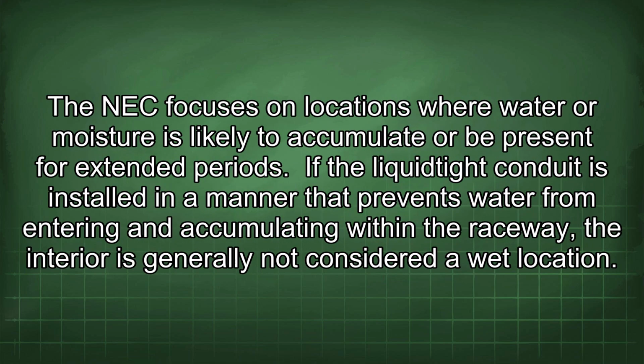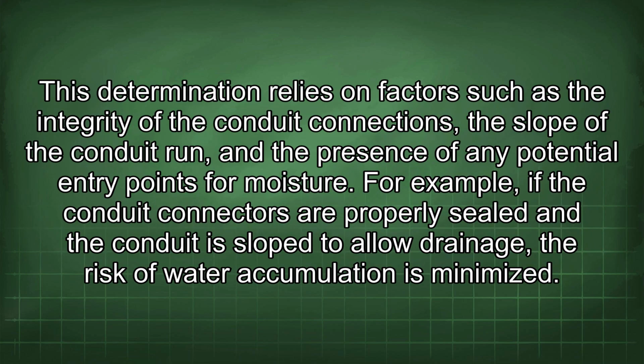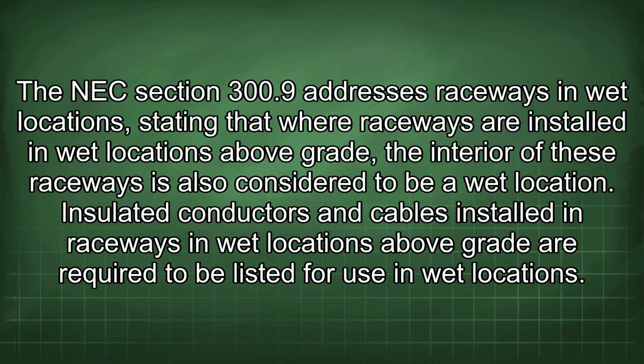The NEC focuses on locations where water or moisture is likely to accumulate or be present for extended periods. If the Liquidtight conduit is installed in a manner that prevents water from entering and accumulating within the raceway, the interior is generally not considered a wet location. This determination relies on factors such as the integrity of the conduit connections, the slope of the conduit run, and the presence of any potential entry points for moisture. For example, if the conduit connectors are properly sealed and the conduit is sloped to allow drainage, the risk of water accumulation is minimized.